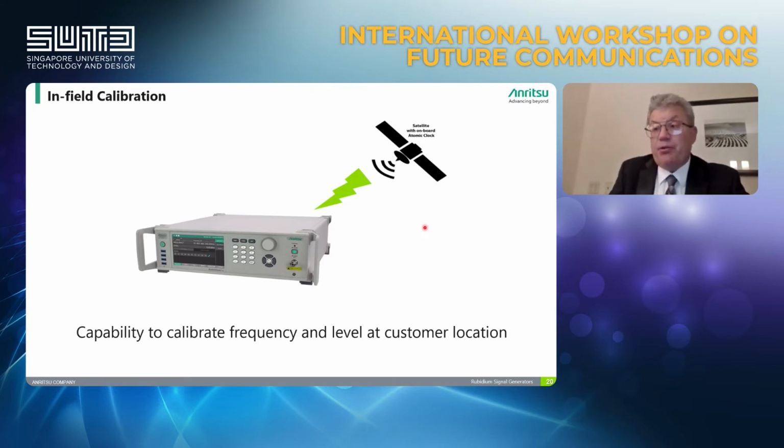And with just a push of a button, we can recalibrate the frequency at the customer location, not sending the unit back to the factory for recalibrating.